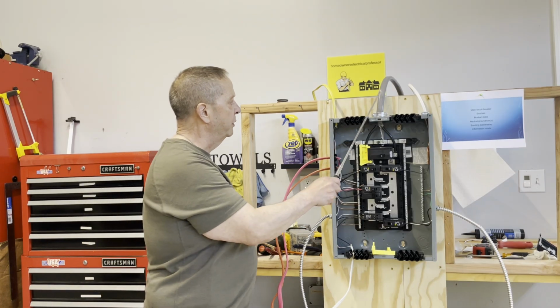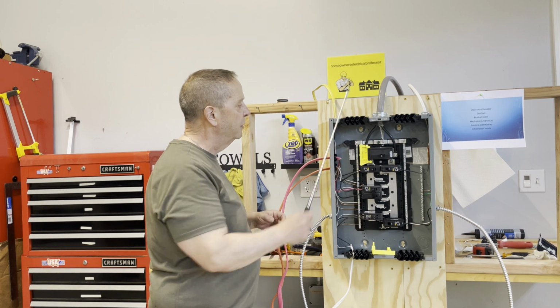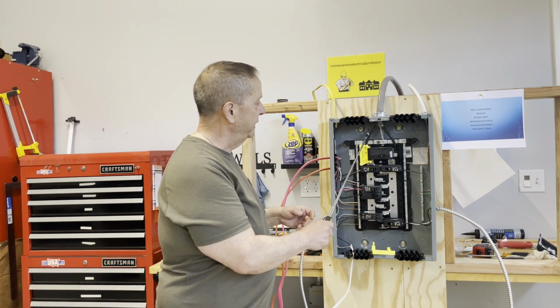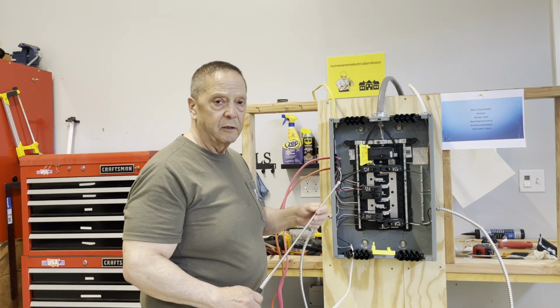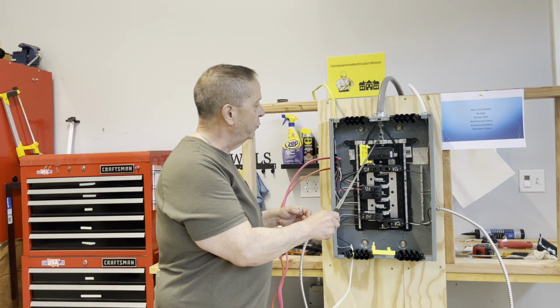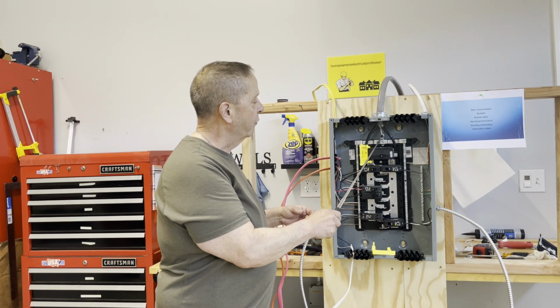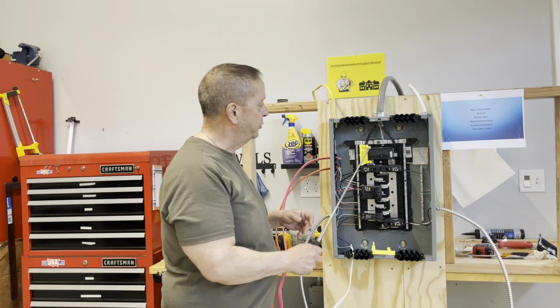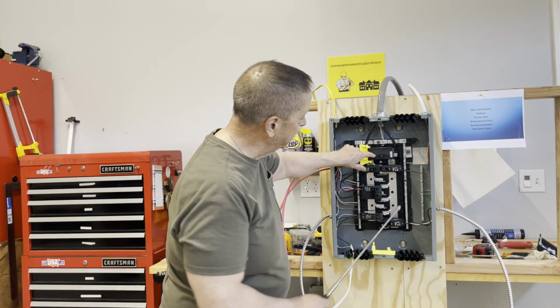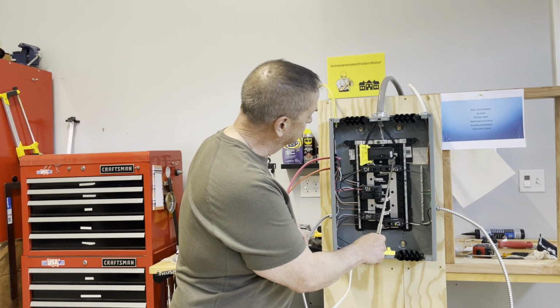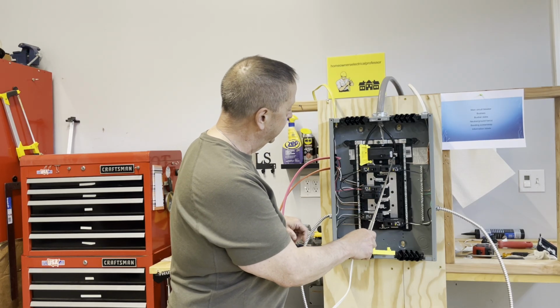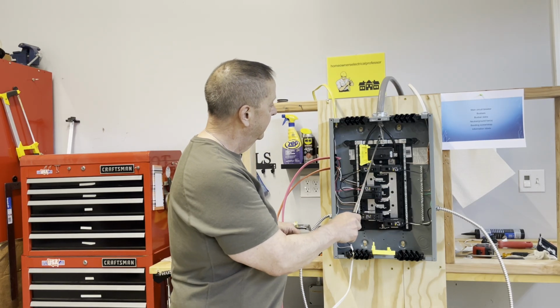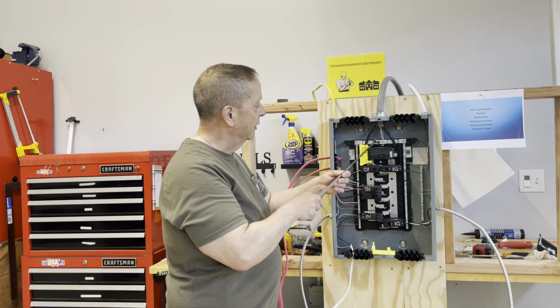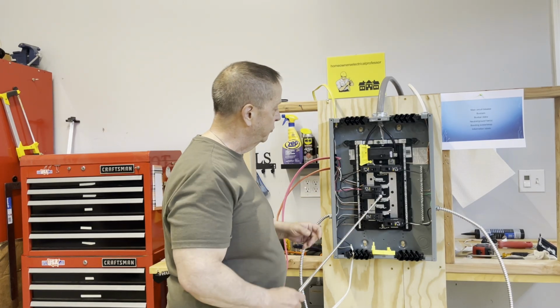We'll start up here with your service entrance cable. That will always be two insulated hot or ungrounded conductors, and one grounded or neutral conductor. As you can see, here's my circuit breaker. It's my main circuit breaker. They're terminated here and here. Here's my neutral along with my green bonding screw.